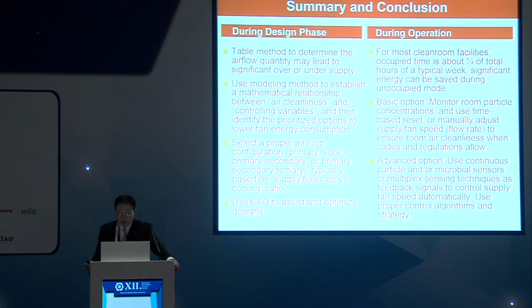A more advanced option is to use continuous particle sensing or even a microbial sensor. Now, in the US and Europe, we have real-time microbial sensors to sense the microbial contamination. With these sensors, you can use them pretty much like a thermostat. They could be laser-based or multiplex sensing systems, providing a feedback signal to control supply fan speed automatically. The keyword is automatically. In other words, you do not want to use a thermostat and then manually adjust the variable flow or the temperature; you let the computer do the work. So clean rooms, of course, need to be controlled automatically, using proper control algorithms and strategy. So roughly about 15 minutes, that concludes my first speech on clean room design.